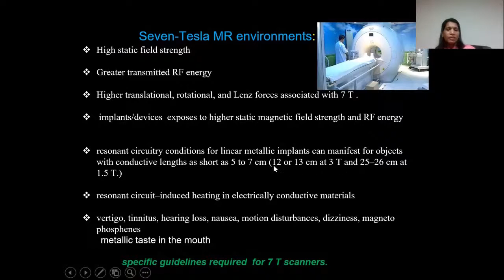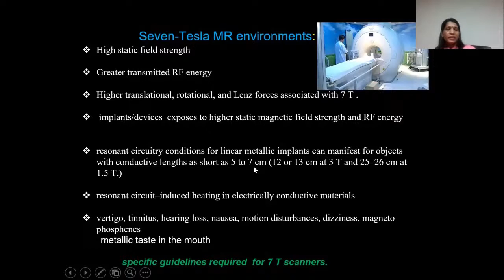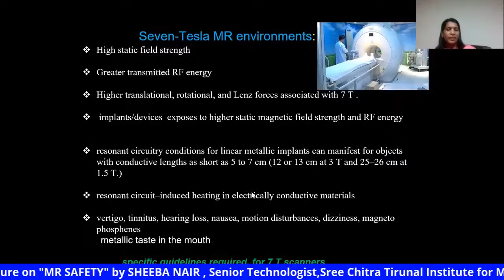Another concern now is the 7 Tesla MRI. With 7 Tesla, the concerns are the higher field strength and greater RF energy. So the translational and rotational forces on the implant are very high, and also there is resonant circuit formation. Actually, in 1.5 Tesla and 3T, the resonant circuit will be formed only at a higher length. But with 7 Tesla, with a length of 5 to 7 centimeters, it will form a resonant circuit, and heating can occur in a 7 Tesla.